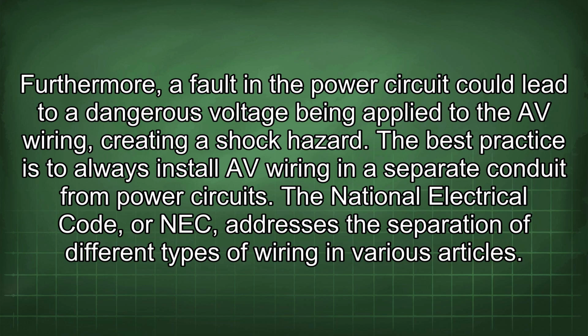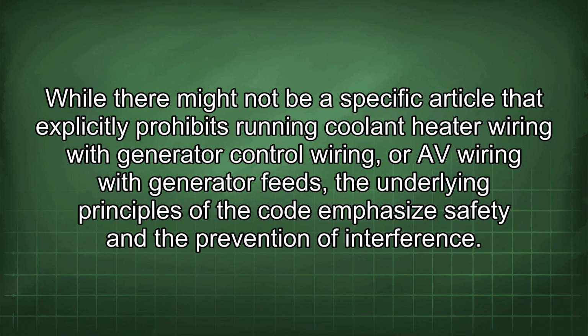Furthermore, a fault in the power circuit could lead to a dangerous voltage being applied to the AV wiring, creating a shock hazard. The best practice is to always install AV wiring in a separate conduit from power circuits. The National Electrical Code, or NEC, addresses the separation of different types of wiring in various articles. While there might not be a specific article that explicitly prohibits running coolant heater wiring with generator control wiring, or AV wiring with generator feeds, the underlying principles of the code emphasize safety and the prevention of interference.